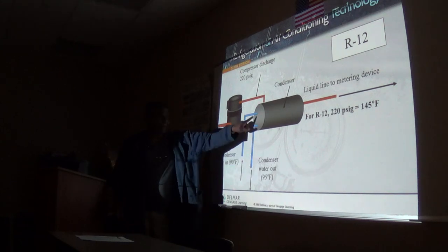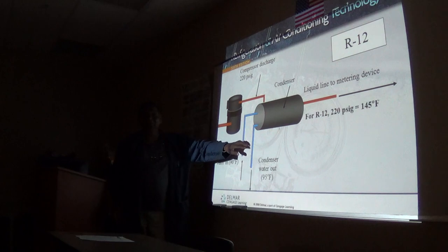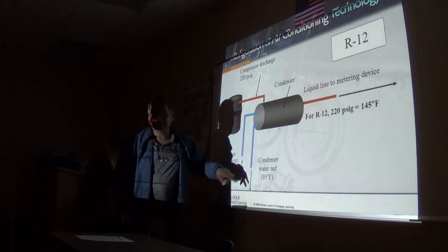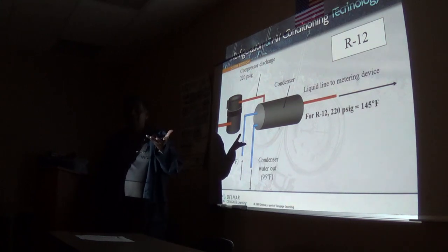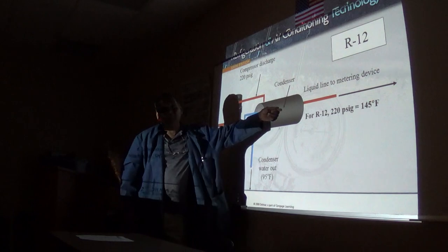I thought they were always looking for 10 degrees with the water out. That's what my regulator is set at, right? And it's going to try to maintain that 10 degrees. But here's the thing. I do not have the flow rate because this is fouled up.